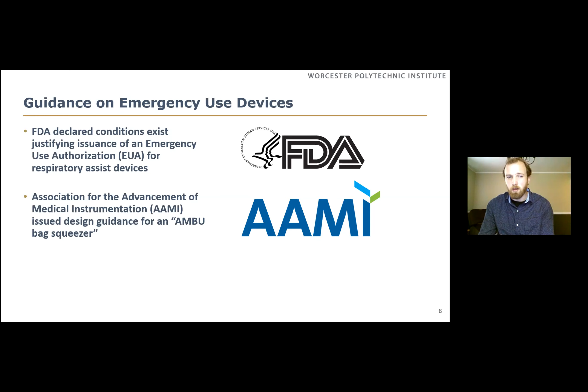And the FDA declared that conditions exist justifying the issuance of an emergency use authorization for respiratory assist devices. And so there are a couple key parameters that a device like this would need to produce. So the I/E ratio is the ratio of inspiration to expiration. For COVID, that is ideally around 1 to 2, but ideally you would have a device that's adjustable from about 1 to 1 to 1 to 4.